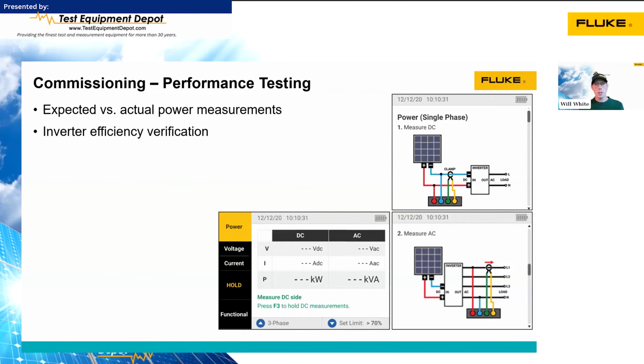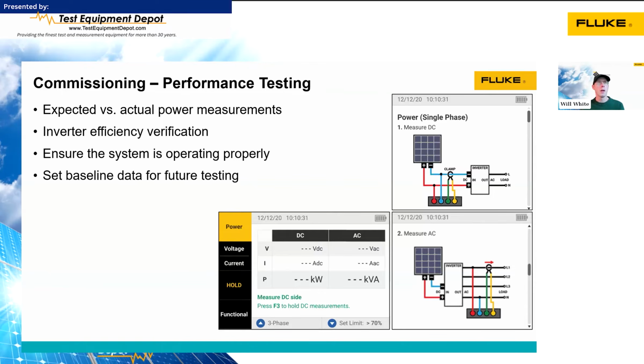Finally, in commissioning, we can do performance testing. So making sure the system is actually producing the amount of power that it should be. We're comparing what we designed it for to what it actually is performing. We can also do inverter efficiency measurements at this point as well. A lot of times we're going to use the data acquisition system included with the system, either the monitoring from the inverter manufacturer or the monitoring that we installed at the system to see how much the power output is compared to what we would expect it to be.